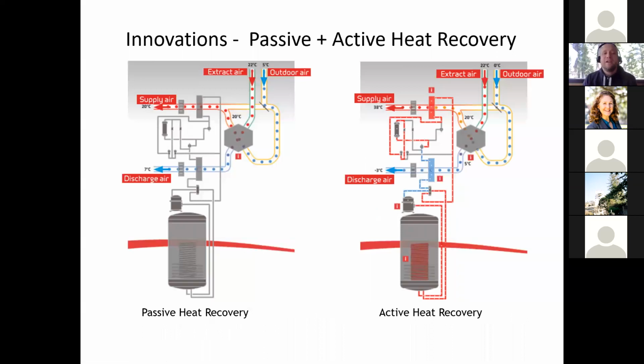So it's a little complicated, but the idea is that air that's being pulled out of your building first goes through a heat recovery plate to preheat your outside air. So it's stealing a little heat there. And then we have an evaporator coil located in that airstream to steal even more heat out of the air to heat your domestic hot water with the heat pump. So really effective system. It can do dehumidification, ventilation, heat recovery, all the bells and whistles that I like in a mechanical system, especially for a home.